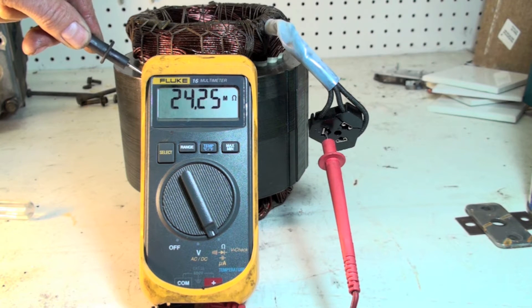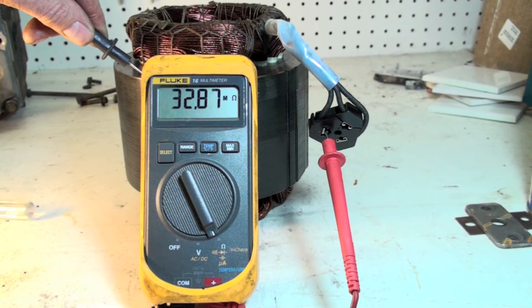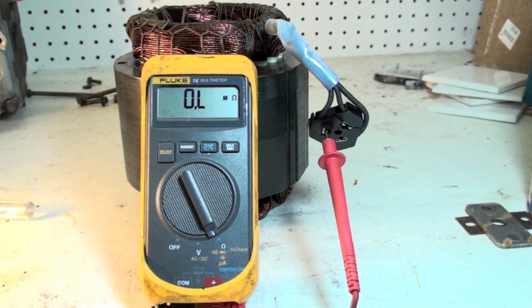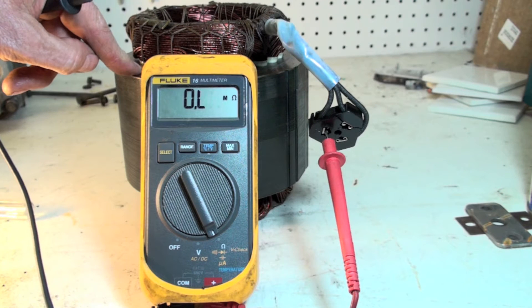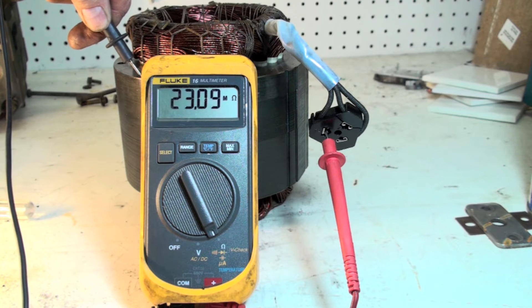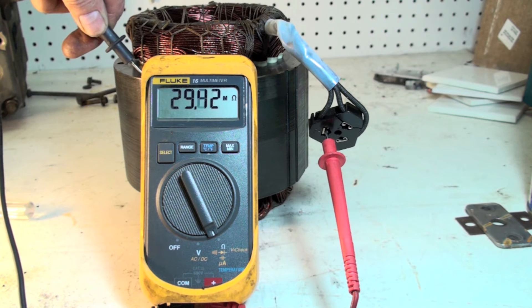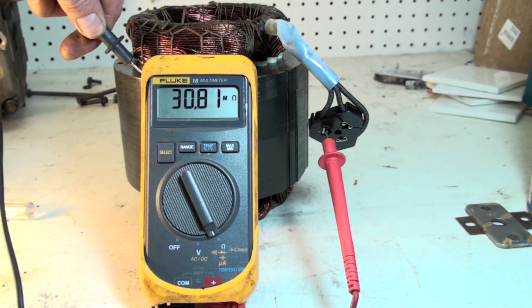We're in mega ohms now and I'm checking the chassis ground. I'm getting a variable reading — 26, 27, 28 mega ohms. That's pretty high, showing about 30 million ohms right now. You might think that's okay, but it really isn't. This thing should read OL when I go from any of these windings to the chassis — in this case the magnet — and it should read OL every time.